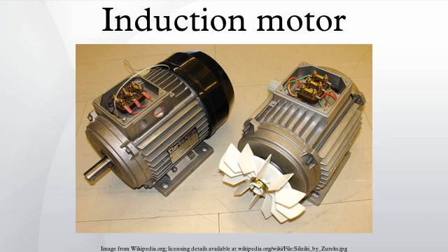Principle of operation. In both induction and synchronous motors, the AC power supplied to the motor's stator creates a magnetic field that rotates in time with the AC oscillations. Whereas a synchronous motor's rotor turns at the same rate as the stator field, an induction motor's rotor rotates at a slower speed than the stator field. The induction motor stator's magnetic field is therefore changing or rotating relative to the rotor.